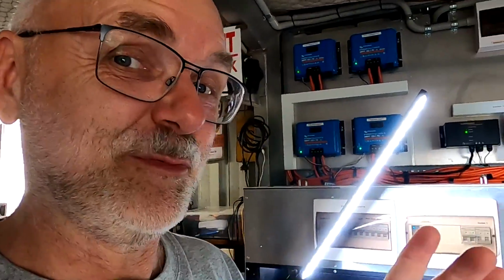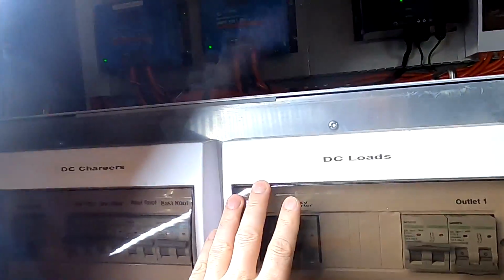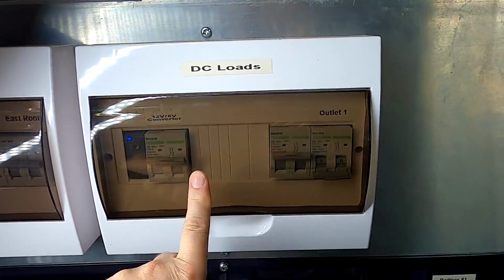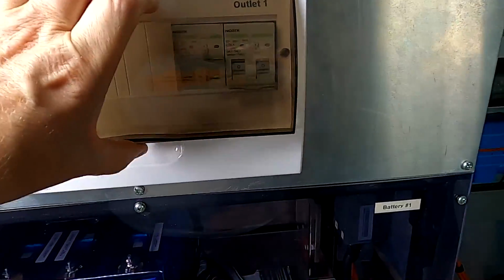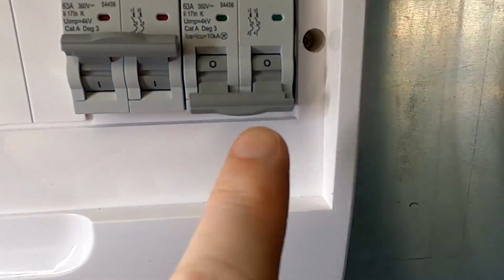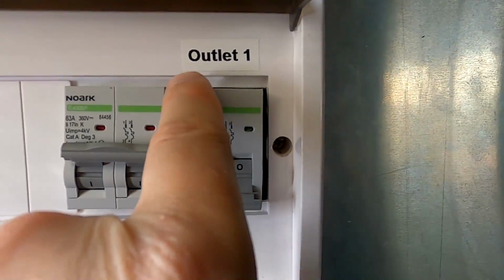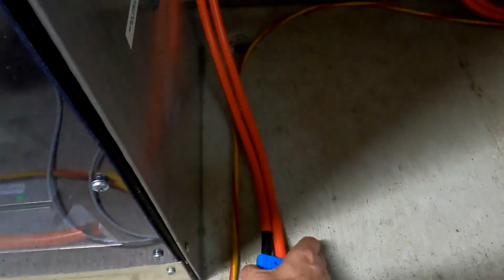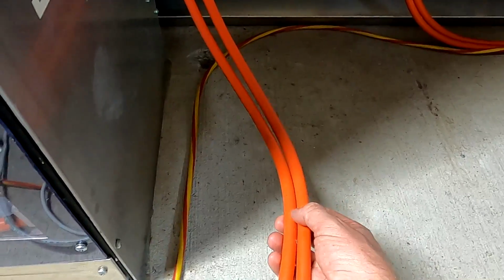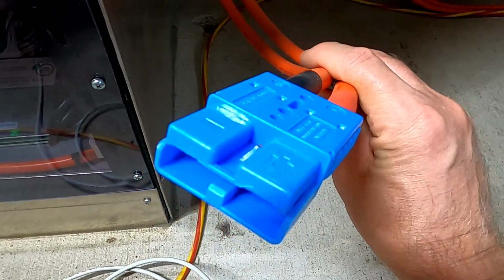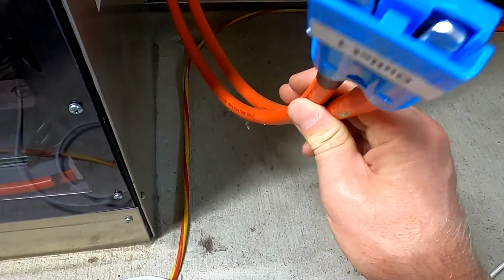And I thought about how to do this quickly and just temporarily, and I came up with an idea which involves this panel here, it's our DC load panel. We have one 63 amp circuit breaker here which is not being used. This is called outlet 1, and it goes directly with some 50 mil cable onto a 120 amp Anderson connector. It says it there, outlet 1.